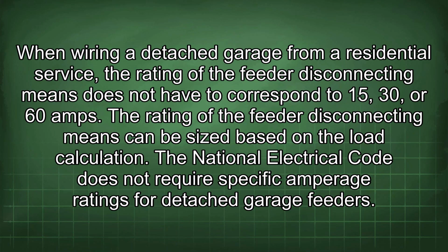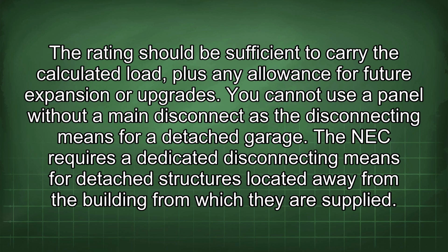When wiring a detached garage from a residential service, the rating of the feeder disconnecting means does not have to correspond to 15, 30, or 60 amps. The rating of the feeder disconnecting means can be sized based on the load calculation. The National Electrical Code does not require specific amperage ratings for detached garage feeders. The rating should be sufficient to carry the calculated load, plus any allowance for future expansion or upgrades.